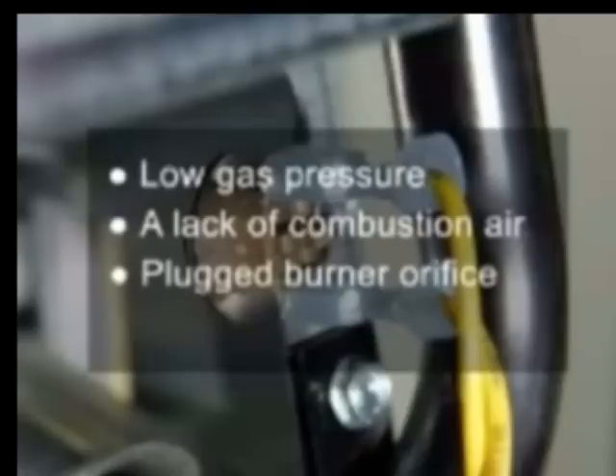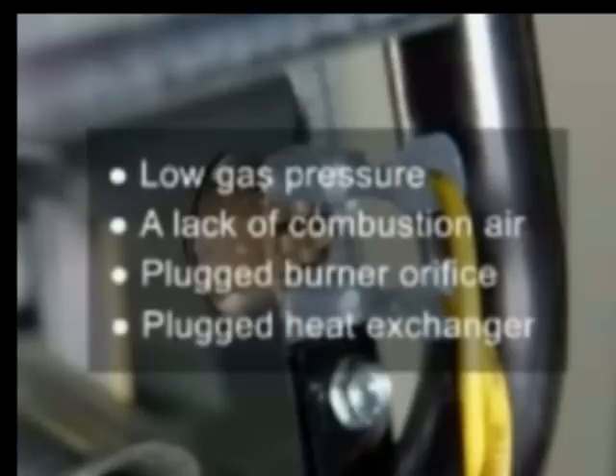Causes of flame rollout trips: Low gas pressure, a lack of combustion air, plugged burner orifice, plugged heat exchanger.